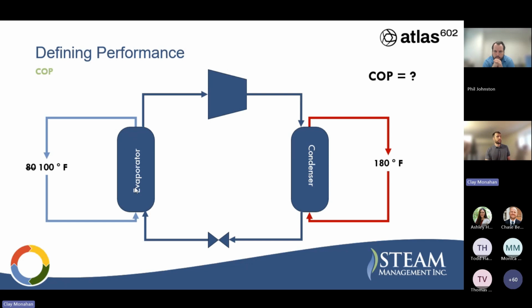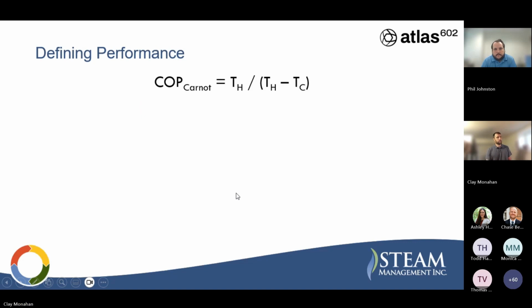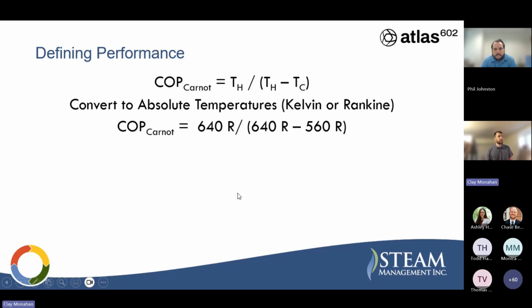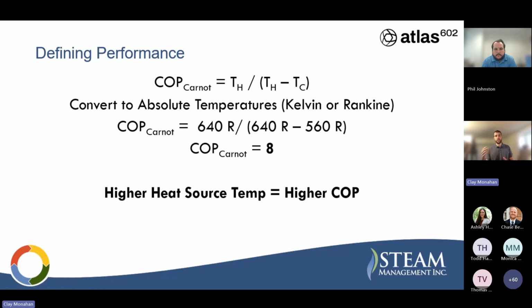Let's do one more example, but instead of increasing the heat sink temperature, let's increase the heat source temperature by 20 degrees. So now we're back to that 80 degree lift, but we have a higher quality heat source. Again, same formula, same conversion. Now we're seeing a COP of 8. So the takeaway there is higher heat source temperature is going to equal higher COP. And that's really the two effects that you want to keep in mind. The higher the heat that you're sourcing, the better the COP is going to be, and the higher you have to go, or the temperature lift that the heat pump has to achieve, the lower the COP is going to be.